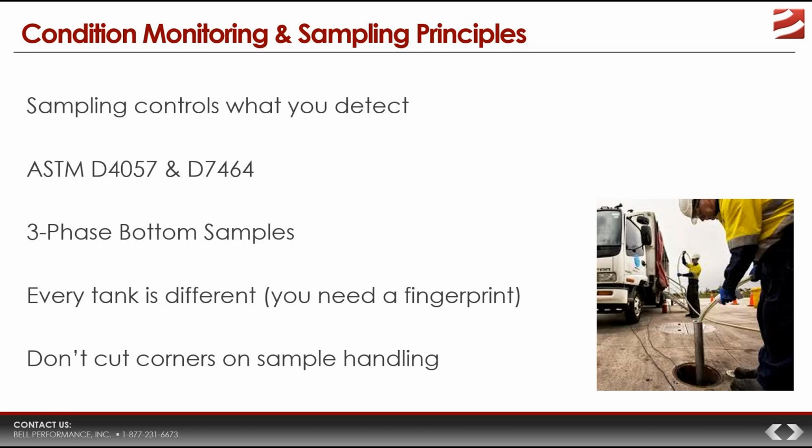What we're talking about here means taking regular samples and testing them for microbial presence. And the recommendation, as we covered in our previous webinar, is sampling 3 times per control interval for your tank. Now, how long is a control interval? Well, it depends on your tank, since the control interval is defined as the amount of time it takes for microbial levels to reach a problem point in a given tank.